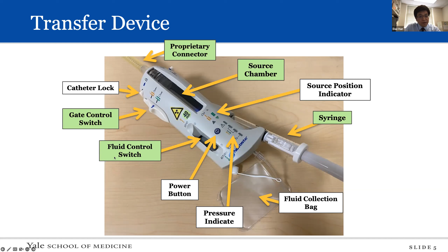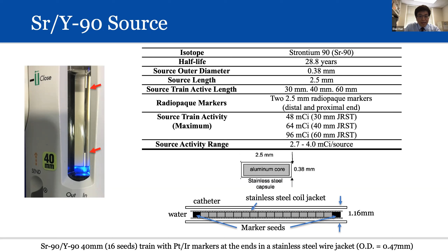This is the source chamber in the transfer device. You can see it has acrylic windows, and you can see the source, which is a 40mm source. And then the Novoste system uses the strontium-90/yttrium-90 source, which is a pure beta emitting source. The sources are enclosed within a stainless steel jacket with 2 radio-opaque markers on each side, and each seed is 2.5mm in length.